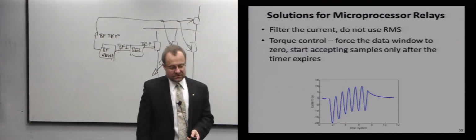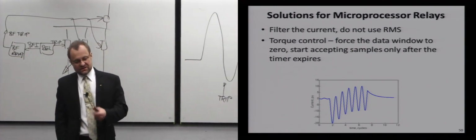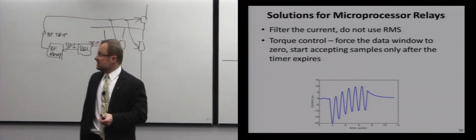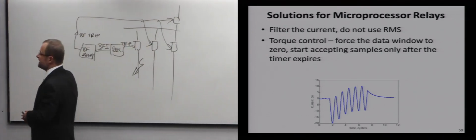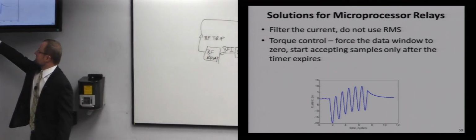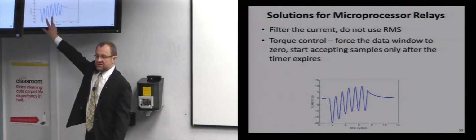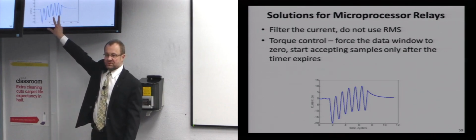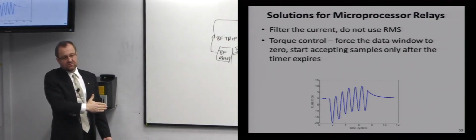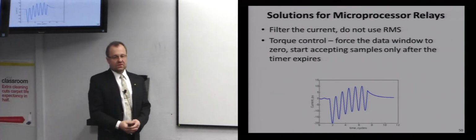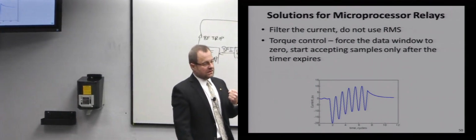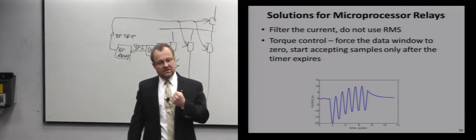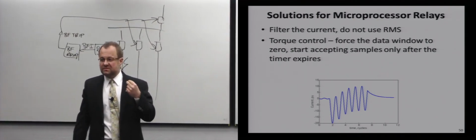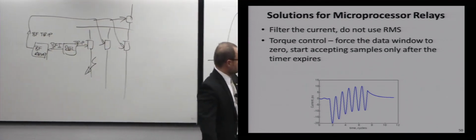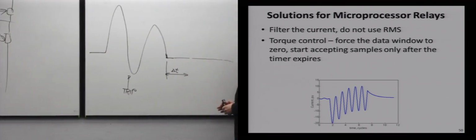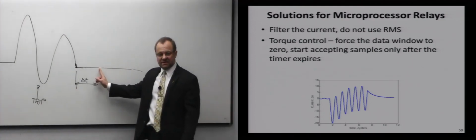So another idea was torque control, meaning that, and this is how the heuristics come into play, you don't let your filter get filled with this high current. Because when you energize it all the way to 20 per unit, now it will have to take some time to realize that it's 0 per unit, right? So you hold the filter back, you fill it with zeros, and only start using real samples after the timer expired.